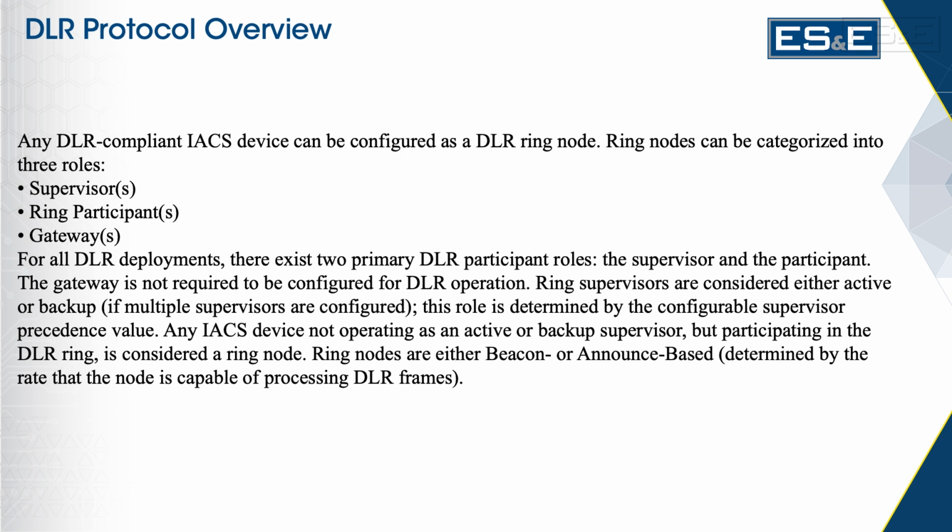One of the biggest things to point out is the convergence time of DLR is 3 milliseconds or less. I don't know if you guys have heard of or know about Spanning Tree Protocol, but that could be 30 seconds convergence time, so you're cutting that down significantly with DLR. With Spanning Tree Protocol, you could have everything connected up in a ring, but if there's a disconnect, you're looking at up to 30 seconds before it converges and figures out, hey, here's how I get back around and pick back up where I left off. So that just doesn't cut it in a production environment. It may cut it in an IT environment, but not in an OT environment.